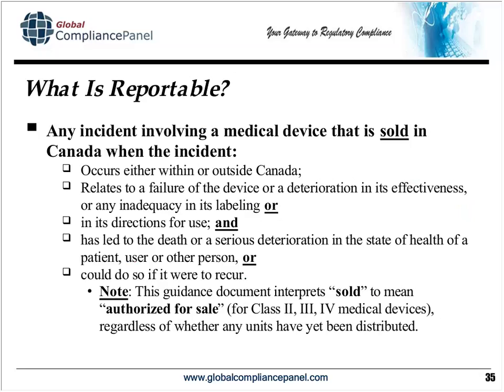Well, any incident involving a medical device that's sold in Canada, when the incident occurs within or outside Canada, an incident that relates to a failure of the device or deterioration or inadequacy in its labeling or directions for use. Then please note the language here: an event that has led to death or serious deterioration, or could do so if it were to recur. Please note how you make a judgment about recurrence. A lot of companies believe that, well, it happened, but the chance of seeing the same recurrence is 1 out of a billion or 1 out of a million, and then 1 month later they have the same problem. Within a month they have the same problem 3 times.